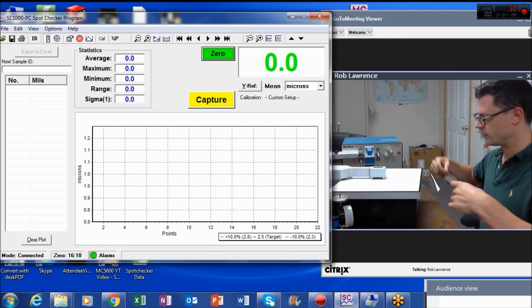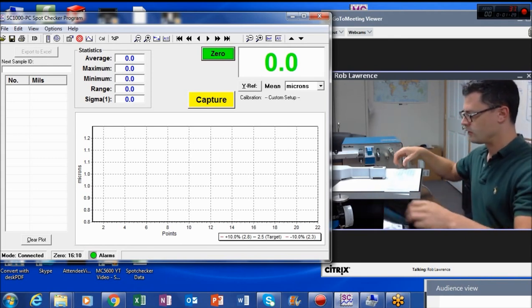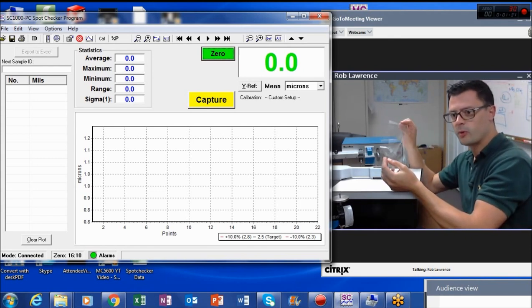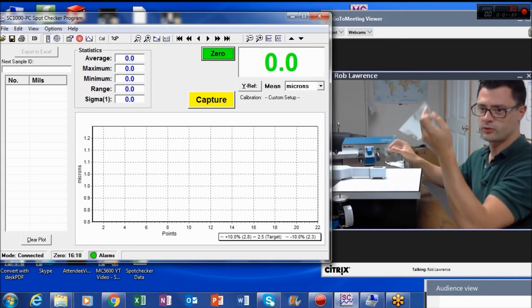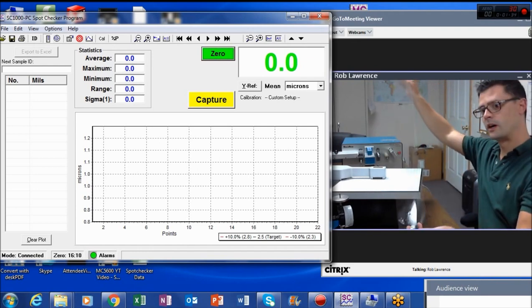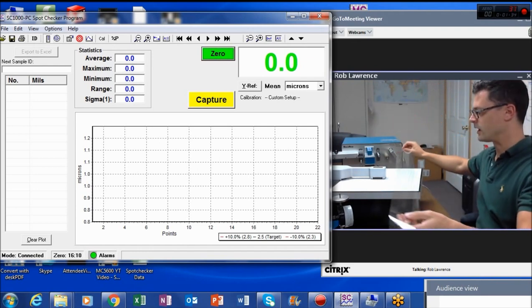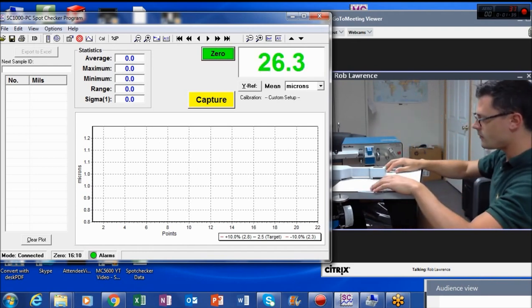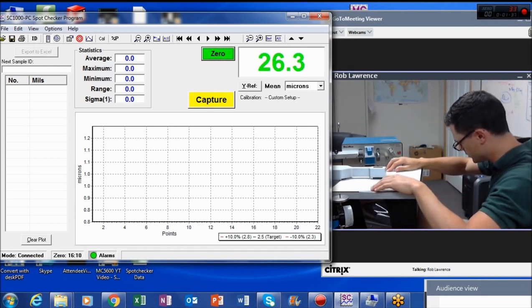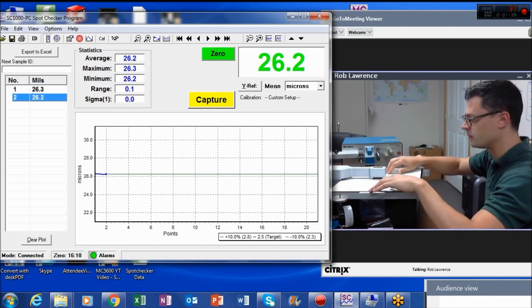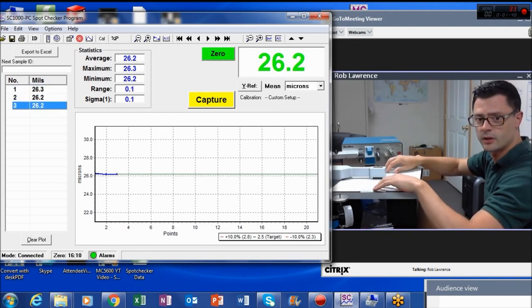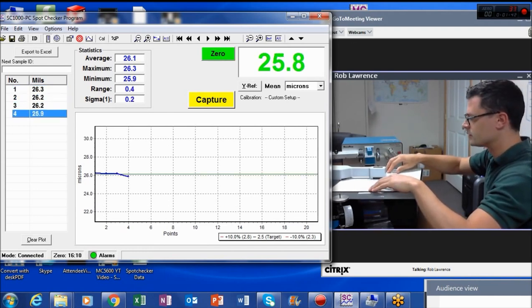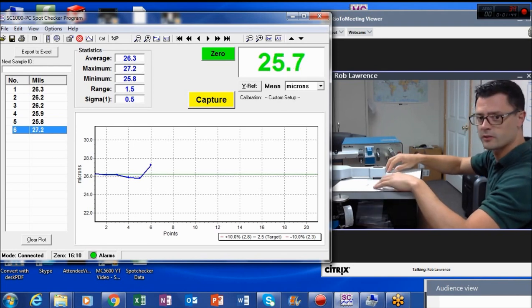Now you can use this gauge to take multiple readings on a film strip, for example, like if you wanted to do a check offline. All you have to do is click this foot pedal, and every time I do, it captures my reading. As you can see, you've got a pretty uniform film here.